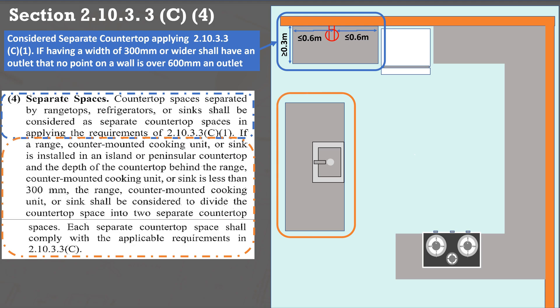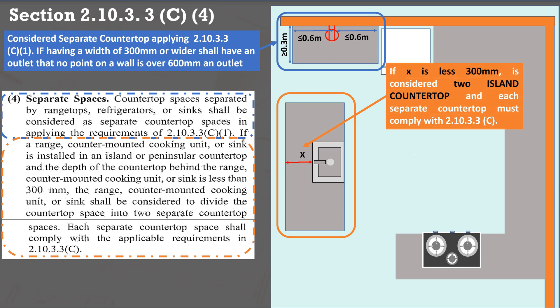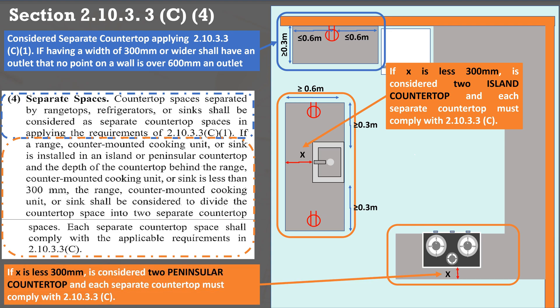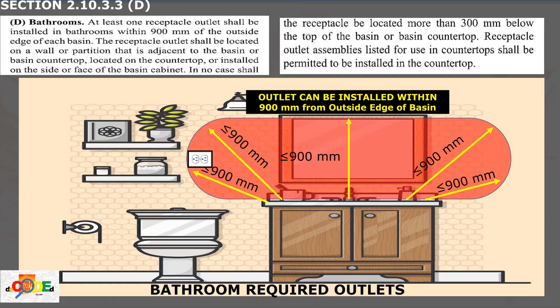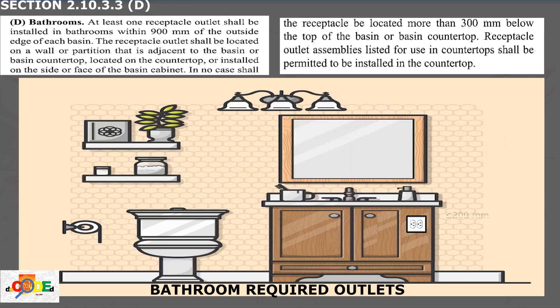If an island countertop is separated by a range, counter-mounted cooking unit, or sink, and if X is less than 300 mm, this is considered a two-island countertop and must comply with 2.10.3.3C — any island countertop 600 mm or more on one side and 300 mm or more on the other side requires a receptacle outlet. Similarly, for peninsular countertops, if X is less than 300 mm, it is considered two peninsular countertops and must comply with 2.10.3.3C. Required outlets in bathrooms shall be within 900 mm of the outside edge of each basin, and shall not be located more than 300 mm below the top of the basin or basin countertop.